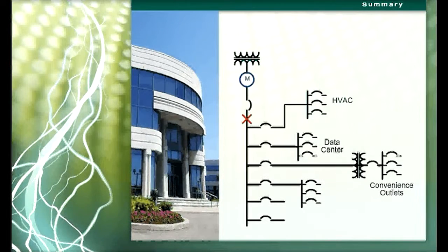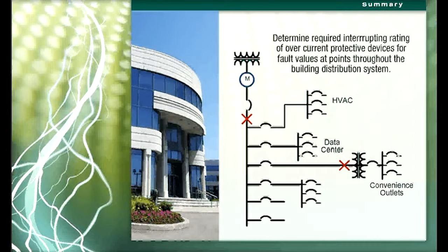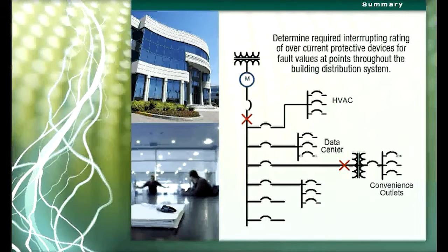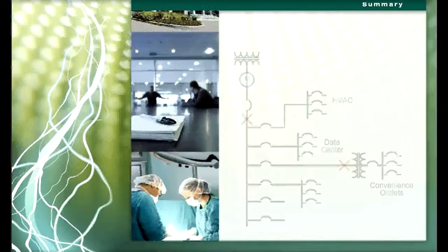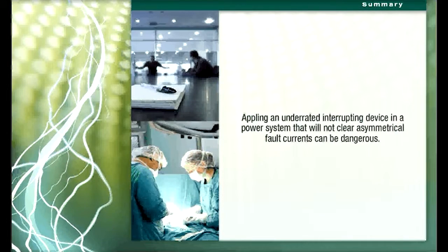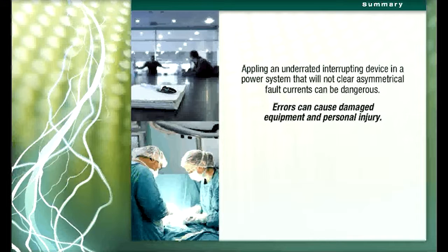The obvious concern for determining the various fault values at points throughout the building distribution system is to determine the required interrupting rating of the overcurrent protective devices. It is generally not problematic to interrupt overload current, but it can be dangerous to apply an underrated interrupting device in a power system that will not clear asymmetrical fault currents. The result of such an error can be damaged equipment and personal injury.